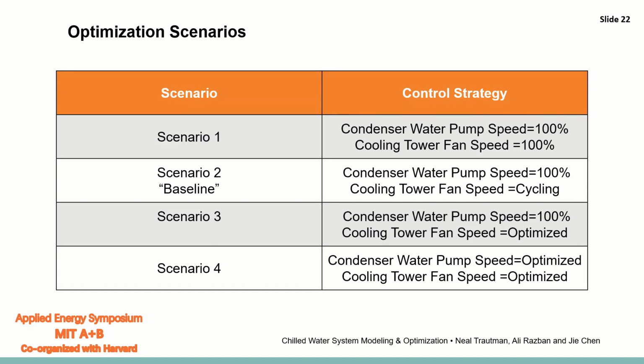That brings us to our different optimization scenarios. So scenario one, we decided to not control either the condenser water pump or the cooling tower fan, run them both at 100% speed. Scenario two was the baseline scenario, their current control strategy, where they would cycle the cooling tower fan between 100% and 25% in order to maintain the condenser water temperature at 65 degrees Fahrenheit.